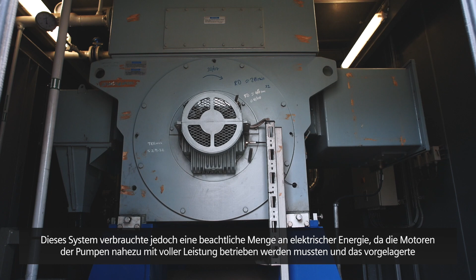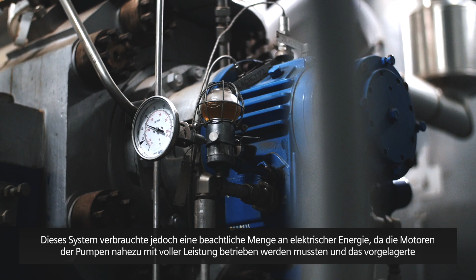We were previously using a mechanical throttling valve control for the feed flow to the HRSG boiler drum in our feed water system. We consumed a considerable amount of electrical energy as the motors of the pumps were running at close to full speed and the upstream high pressure feed water control valve was open to control the flow. This caused severe valve erosion.